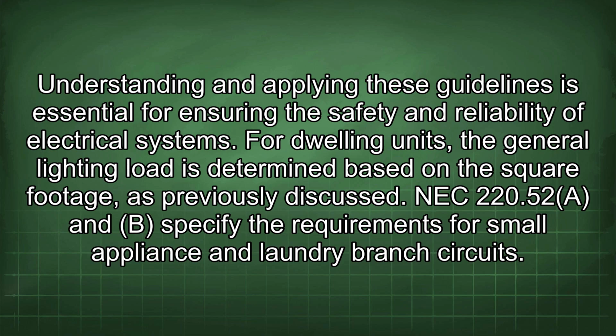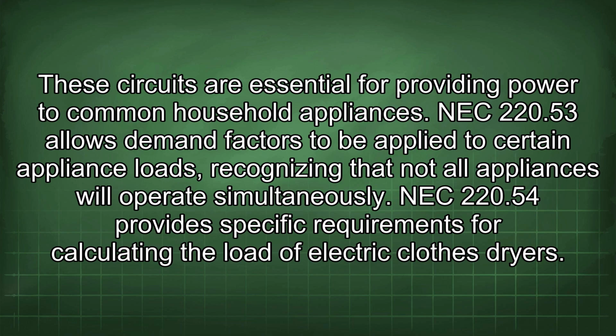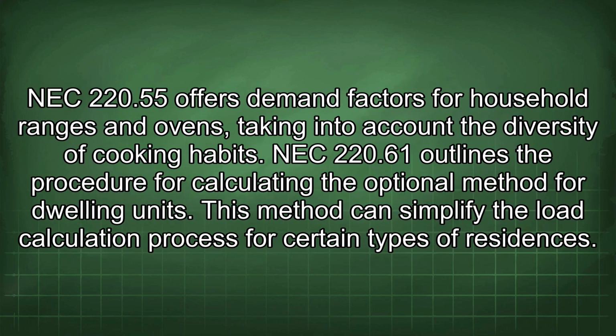For dwelling units, the general lighting load is determined based on the square footage, as previously discussed. NEC 220.52(A) and (B) specify the requirements for small appliance and laundry branch circuits. These circuits are essential for providing power to common household appliances. NEC 220.53 allows demand factors to be applied to certain appliance loads, recognizing that not all appliances will operate simultaneously. NEC 220.54 provides specific requirements for calculating the load of electric clothes dryers. NEC 220.55 offers demand factors for household ranges and ovens, taking into account the diversity of cooking habits.